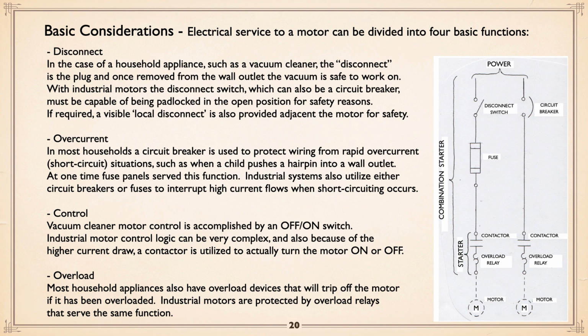Now, if you look at the little drawing on the right, it shows all these things. One on the left bank is a disconnect switch and fuse. On the right is a circuit breaker, which provides both disconnect and overcurrent protection. Then the contactor, which is turning the motor on and off. Overload relay, which is catching the situation of overload on the motor. Now, contactor to begin with. When you add an overload relay to a contactor, it becomes a starter. And if you add either disconnect and fuse or circuit breaker to a starter, you get a combination starter. See all these fancy expressions you're now experts on? Okay, fine.